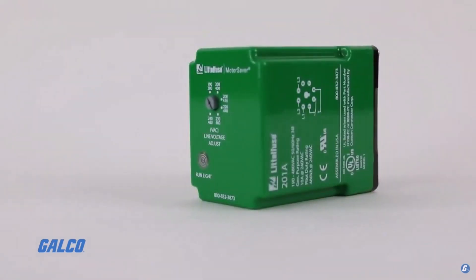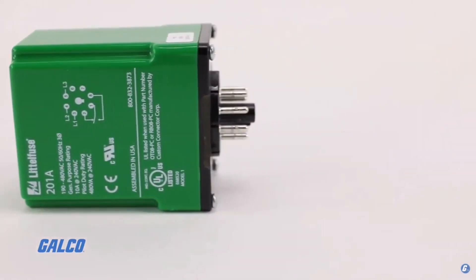The 201A monitor can recognize and distinguish between low-voltage conditions, phase loss, phase reversal, and voltage unbalance. When a harmful power event is detected, the voltage monitor's output relay is deactivated after trip delay.